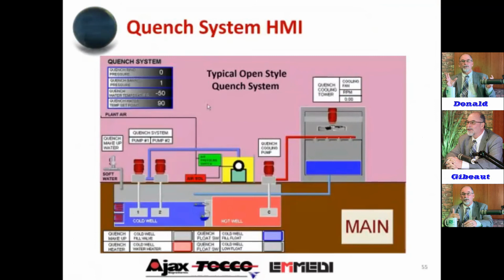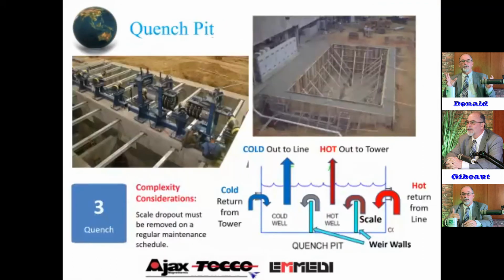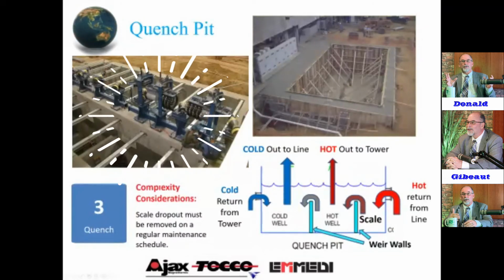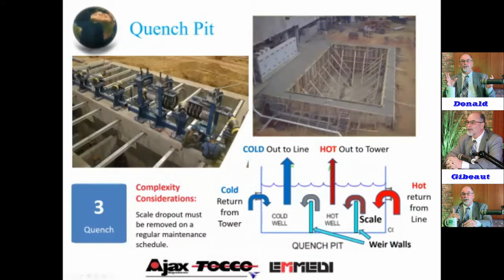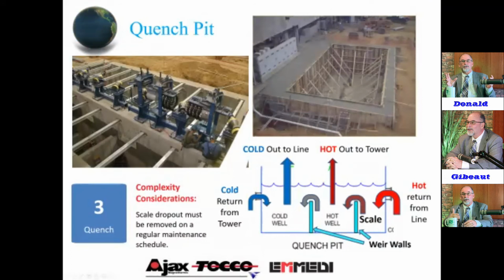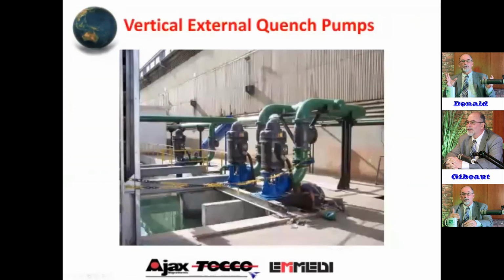Here's just in our controls, the HMI, one screen that comes up that monitors all the pumps throughout this quench system. Here is the physical pits. You saw this picture earlier on. This is an in-plant quench system right below the quench line. This particular one was rated at 36 tons an hour, and you can see the weir walls and the spillover in this pit. This is an outdoor pit that's covered with the grates. But again, just like we described, you've got your scale collection, then the water spills over this spillway into the hot well, pumped through the tower and a centrifugal separator to get the loose scale out of the water before coming over here to the cold well and then pumped back through the system.